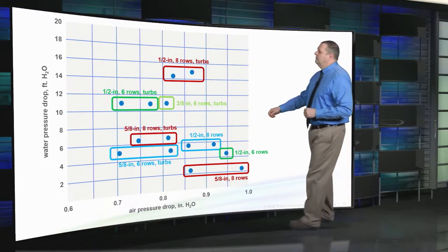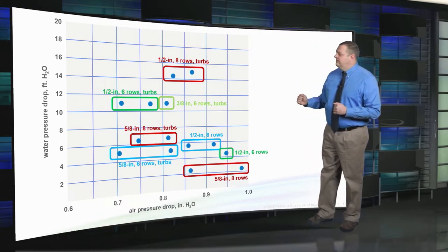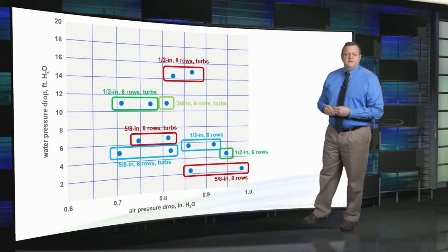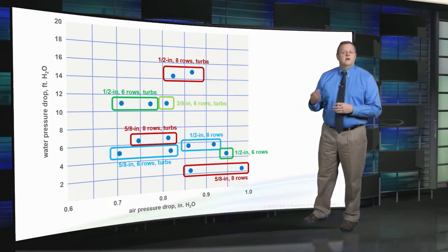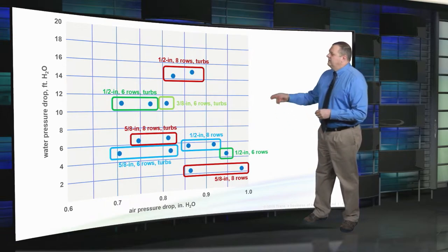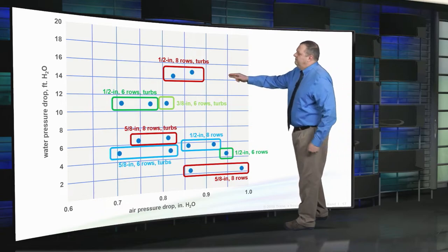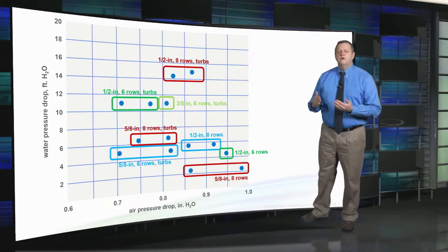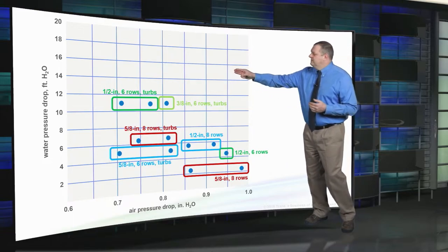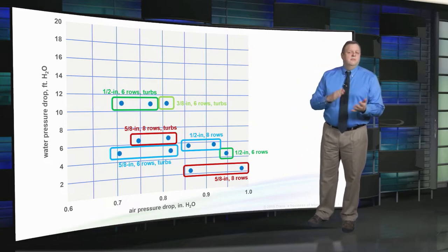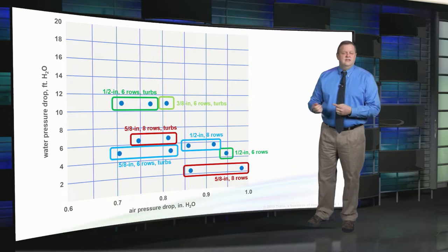Considering relative cost: the 3/8 inch tube coil is cheapest, depicted in light green. The next cheapest are the 6-row 1/2 inch coils. The blue options are a little more expensive — 8 rows with 1/2 inch tubes, or 6 rows with 5/8 inch tubes. And the red coils are the most expensive — all 8-row coils. For this application, why spend more on 8 rows with 1/2 inch tubes if you can get lower air and water pressure drop at a lower price with 6 rows? Similarly, with 5/8 inch tubes, 6 rows provides lower air pressure drop at lower cost.